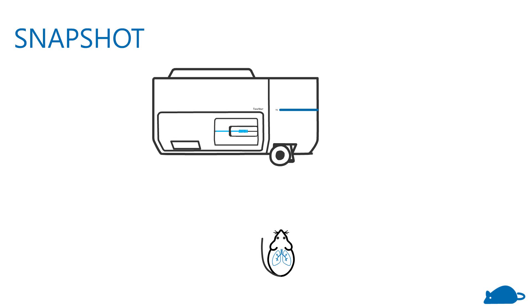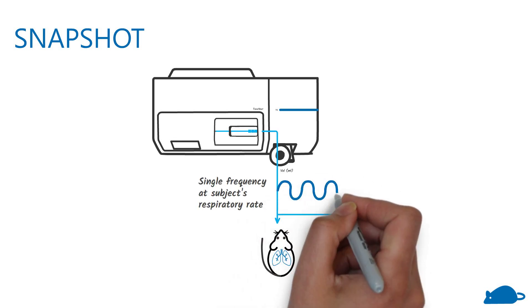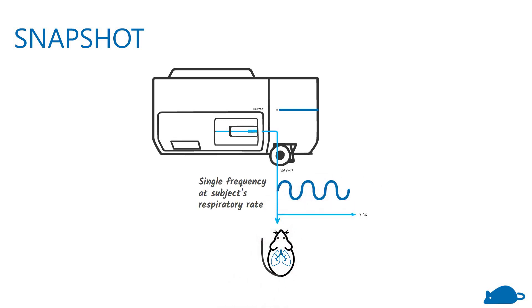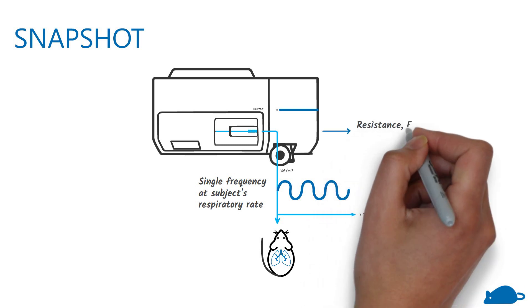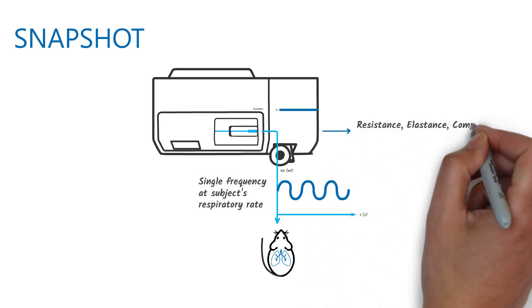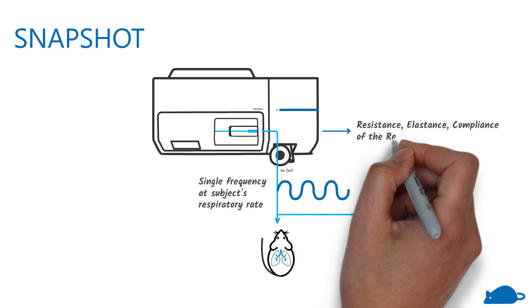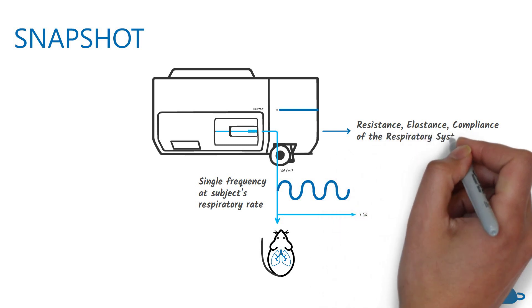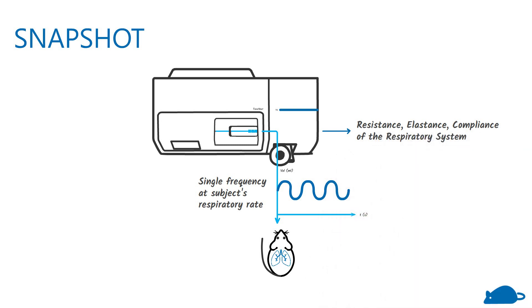In the snapshot measurement, the lungs are given a single frequency signal matched to the subject's respiratory rate. Using the signal, the flexi-vent calculates the resistance, elastance, and compliance of the respiratory system.